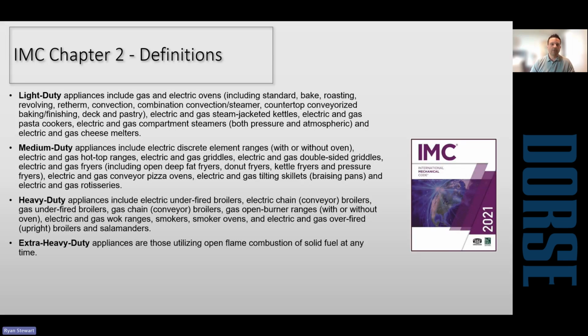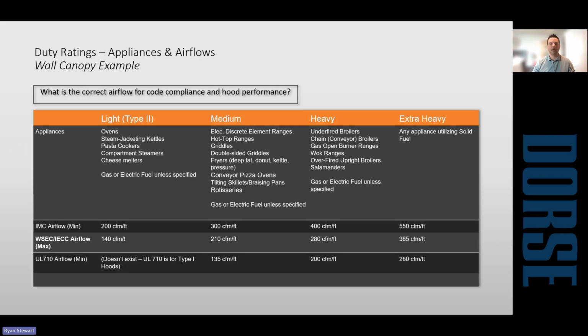So as far as the appliance duties are concerned, you can reference Chapter 2, the definitions in the IMC. For each of the duty classes, it's outlined what appliances fall into those classes. And I put that into a table here, and then included what the International Mechanical Code has for minimum airflows for the appliance duty. Again, these UL 710 hoods are exempt from that section of the code. The next line down is what your maximum flow rate is per foot for the appliance duty to meet Washington State Energy Code and ASHRAE 90.1. And then down at the bottom is the UL 710 minimum airflows for those appliance duties. For a design airflow, you're going to fall someplace in between UL 710, which is your perfect-world lab condition, and what code says your maximum is for the appliance duty.